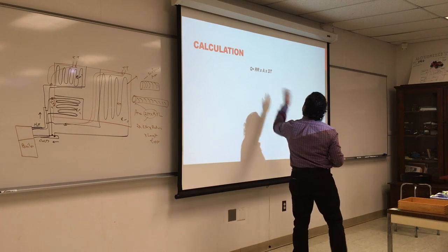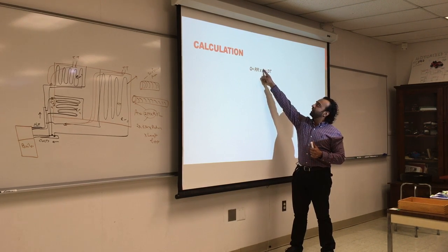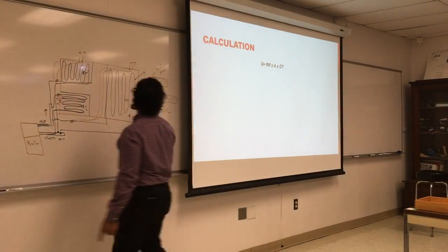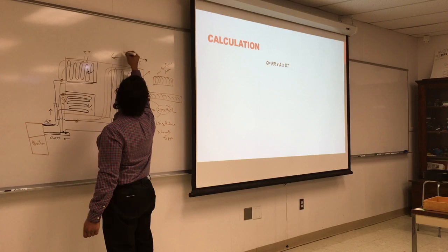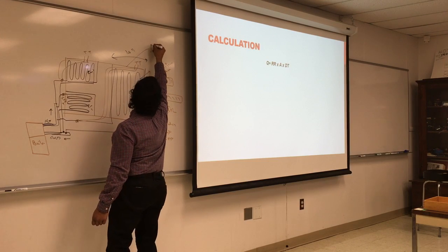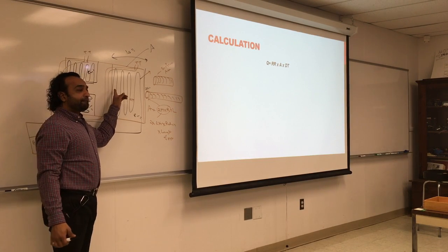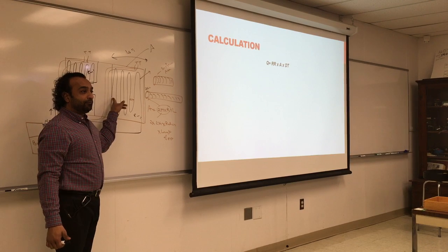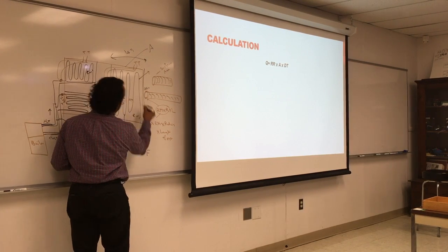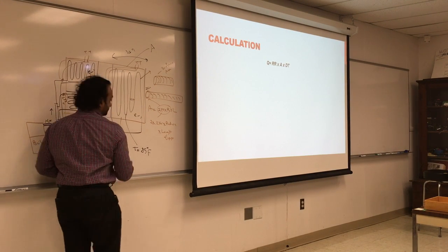And this is our general equation. So in here we have our heat loss equation, area. What area is that? That's the area of the floor. So this is my area here. Not this area, not the pipe area, this is my area. Temperature difference. This is the temperature difference between the room and the pipe. So what is the temperature here in the pipe? Usually 85 degrees. Temperature of the room, 75 or 65.